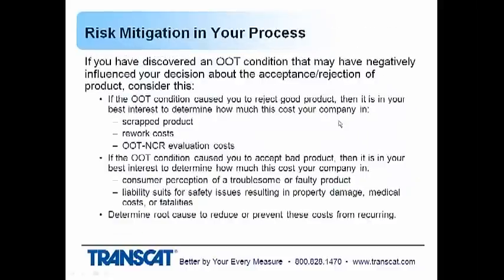So then you get down to the risk mitigation, and that is when you've determined that there's an impact to the product, what do you do with that information? How do you make sure that you fix the problem in your process? Make sure that that instrument is either changed out if you have a reliability issue with it, so you don't have those impact studies that cost you money, or more directly, whether that out-of-tolerance data had an impact on your product being called good or bad in the past calibration interval.